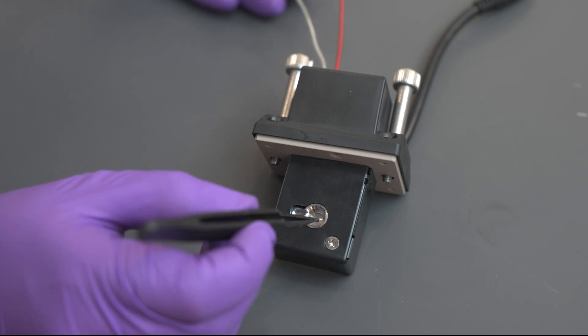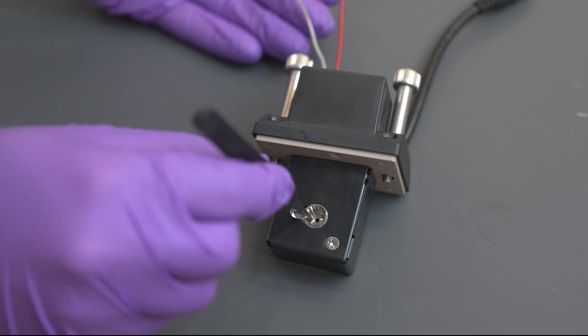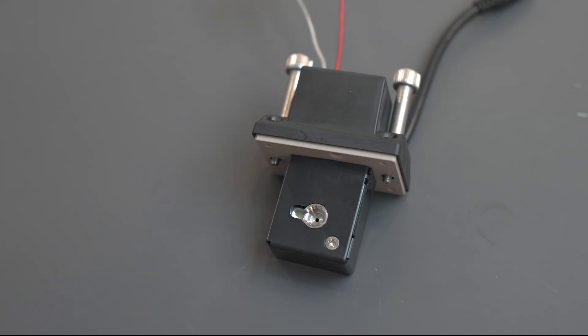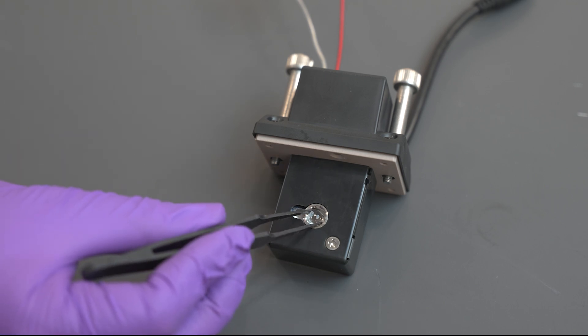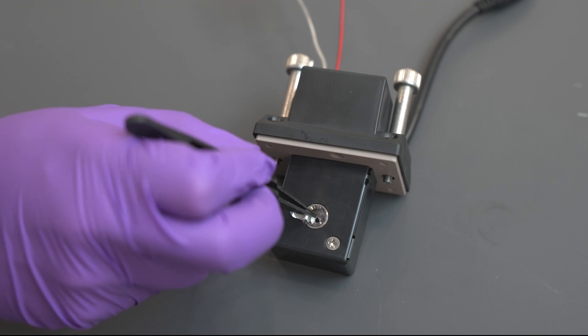Rotate the gasket to push out any air bubbles, preventing it from contacting the surface of the flow cell. Pick up one of the lenses with the plastic tweezers and place it above the gasket, flat side down. Make sure that it is seated properly.